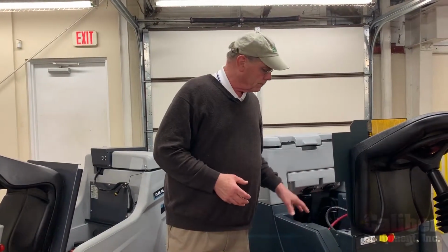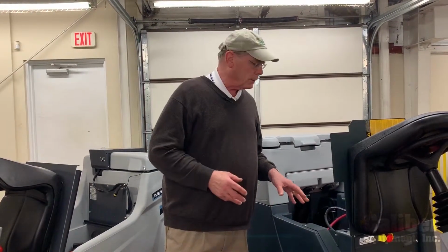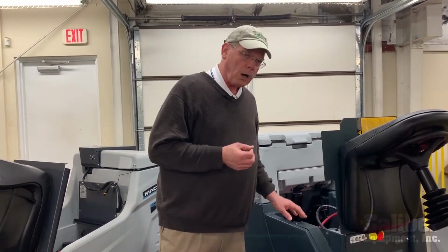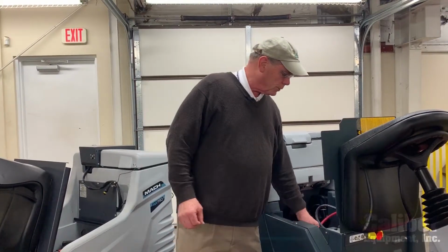So the thing is, we must be very careful when we're handling the batteries. There's another thing that can happen. If batteries are not properly secured or aligned according to the cables in the machine, according to the directions that are printed on most battery cases, you have potential for shorting or arcing. The shorting occurs when you don't tie the cables that connect the batteries properly. That's pretty obvious. But the arcing is when someone hasn't properly secured the terminals.